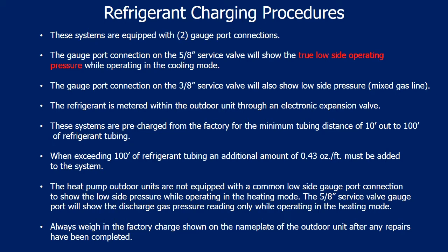These heat pump outdoor models are not equipped to show the true suction pressure when operating in the heating mode. The 5/8 inch gauge access port will show the true discharge pressure when operating in the heating mode. Always weigh in the factory charge as shown on the nameplate of the outdoor unit after any repairs have been made to the refrigerant side of the system. All Panasonic heat pumps will energize the reversing valve in the heating mode.